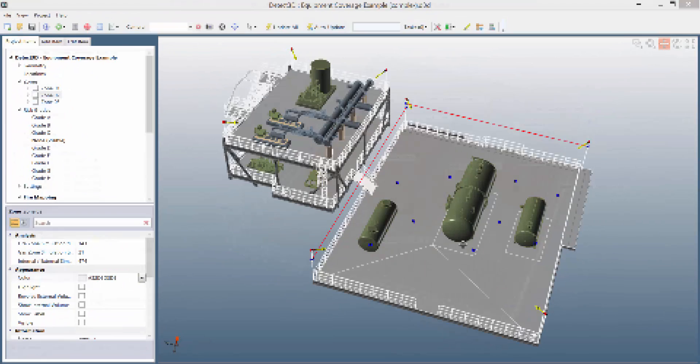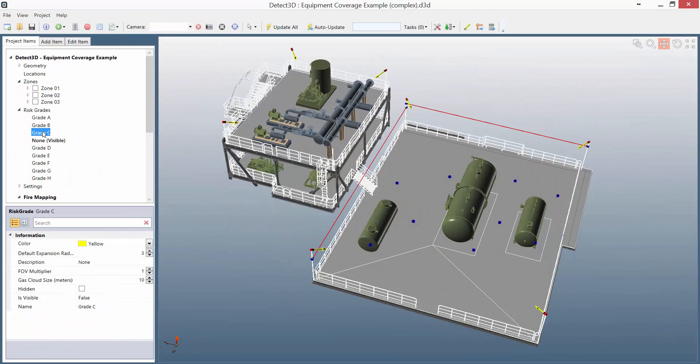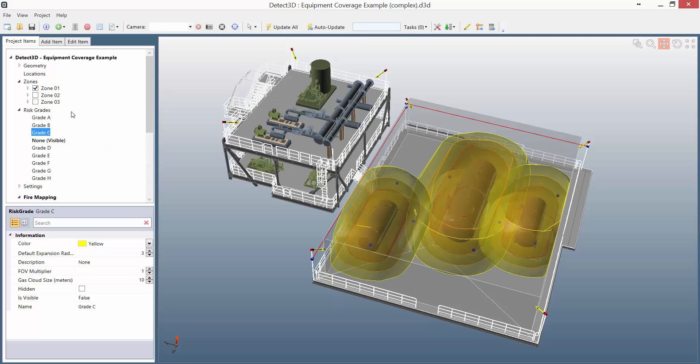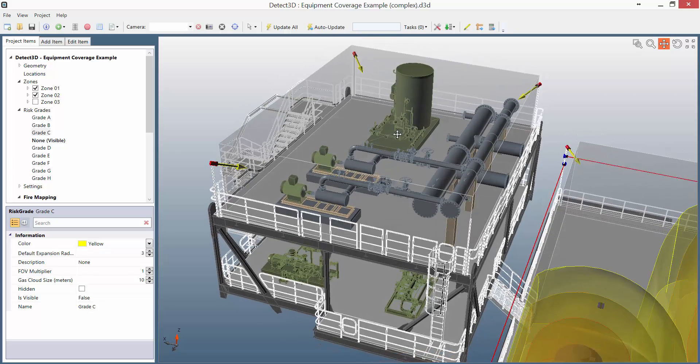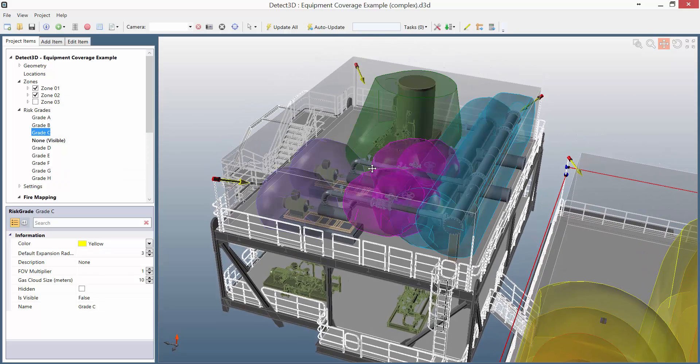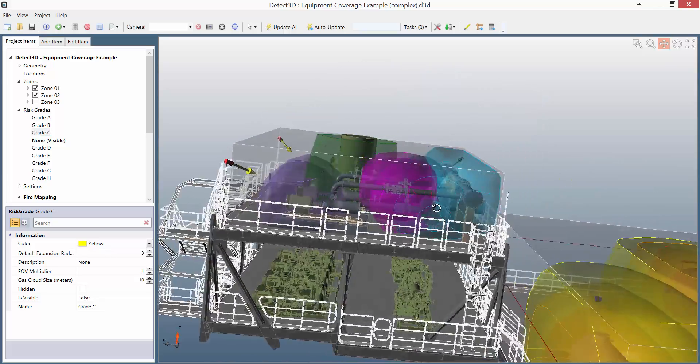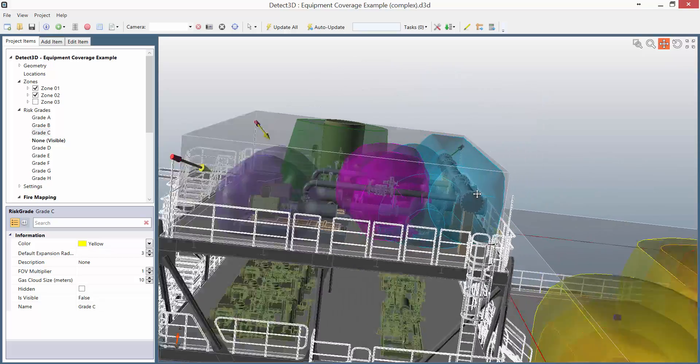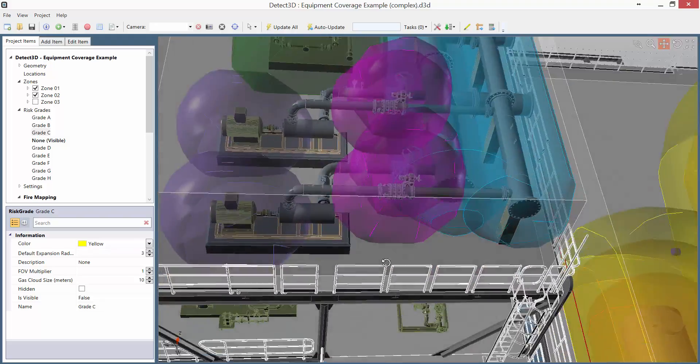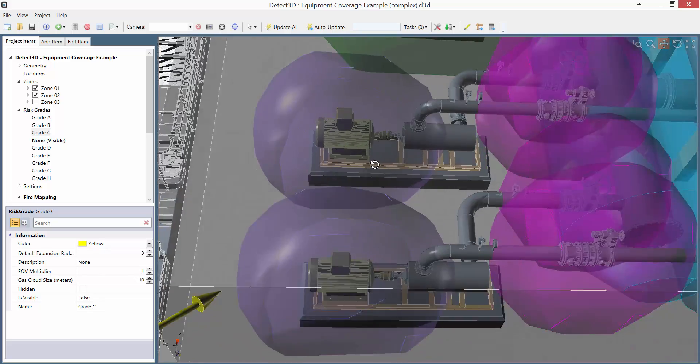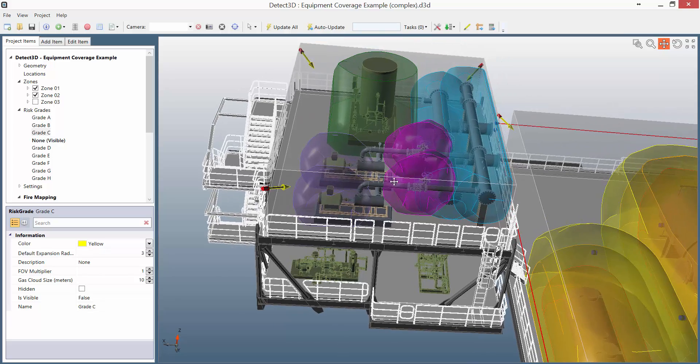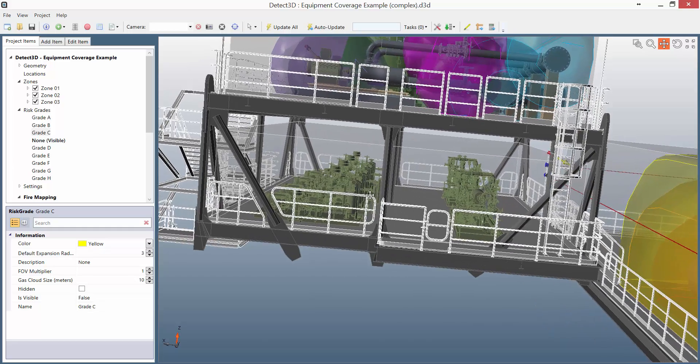You're also not limited to just three risk grades. You can add as many as you want and customize them all to the standards that you're working to. In this more complicated example, I have a total of nine risk grades. And I've used them in a number of subzones around equipment in three well-defined zones. In the first zone, they're set up just as I had them before, but in the second zone that I'm focusing on now, I've used a number of different subzones, all with different risk grades, D, E, F, G, etc. They all have different meanings and different colors, and some surround pipe work, some around flanges, some just around general equipment items. And I can change their name, their color, the radius from the equipment to be anything I want to fit my particular performance standard.